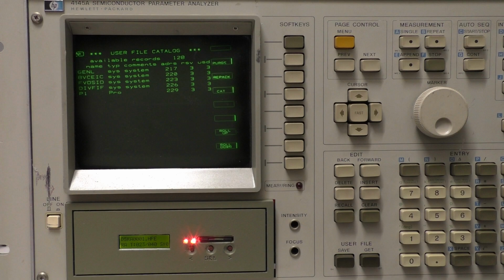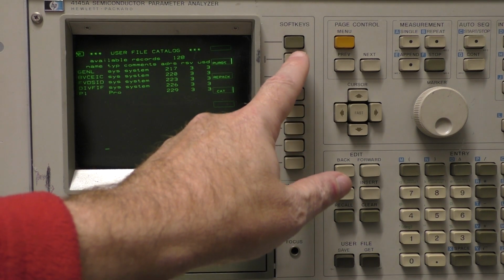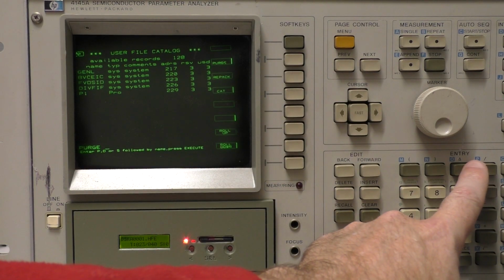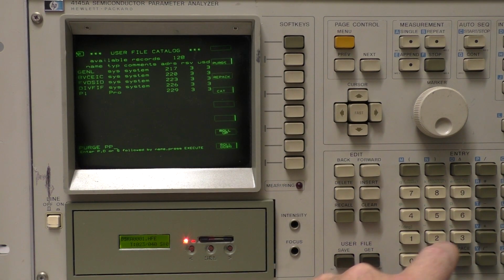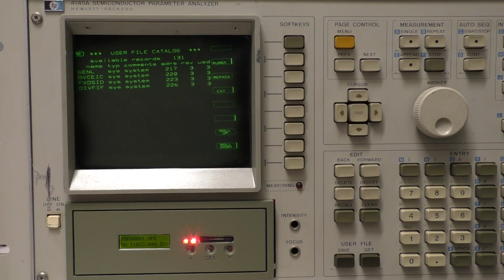Let's ensure we can delete the file. Press Purge. Again we enter a P to set the file type as a program. Now enter the file name, P1. Hit Execute. Perfect. The file has been removed from the SD card. So that's it, we now have an operating 4145A.